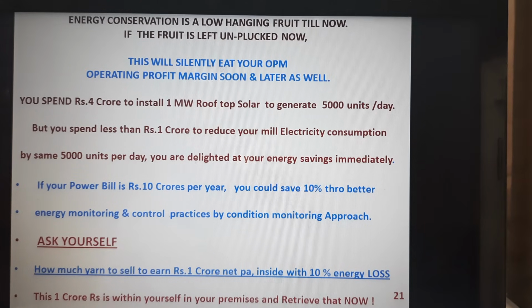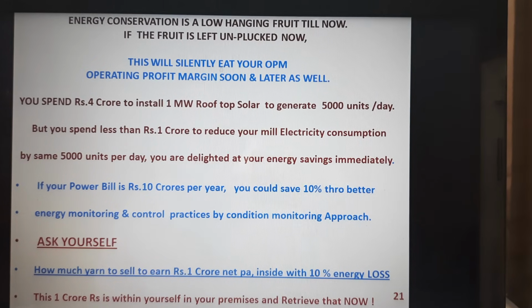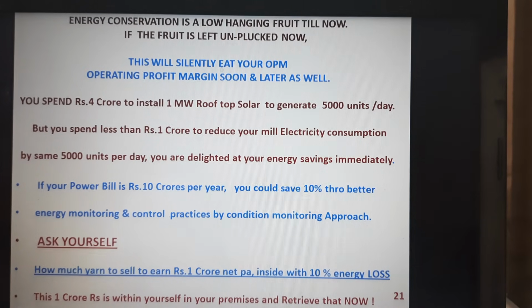If your power bill is around 10 crores per year, you can save around 10% through better energy monitoring. Energy monitoring is a must, then only can control happen. The control and the energy conservation practices can happen through a condition monitored maintenance approach. So you can just ask yourself how much yarn you would have to sell to earn this 1 crore net per annum, because around 10% energy loss is already happening inside. This can be recovered from inside the mill itself. This 1 crore is within yourself, in your premises, and it is time to retrieve that now as such.